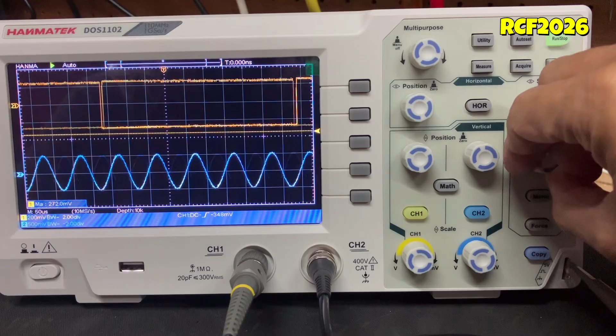However, depending on the two input signals and the current trigger settings, you may find that the waveforms are moving across the screen and are not completely stable. To correct this, press the Trigger menu button and change the trigger source to channel 1. Now adjust the trigger level so that it falls within the voltage range of the channel 1 waveform. Once the trigger point is correctly positioned, the display should become stable.